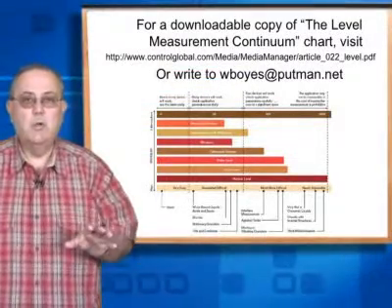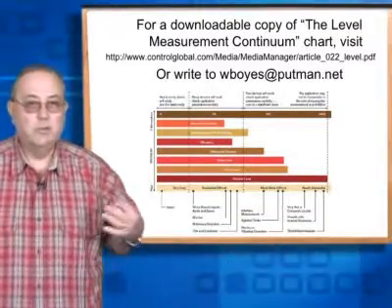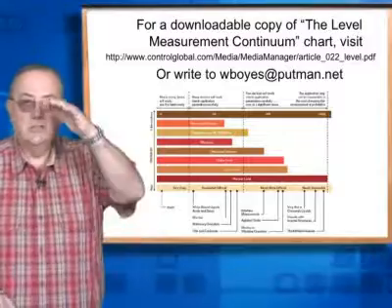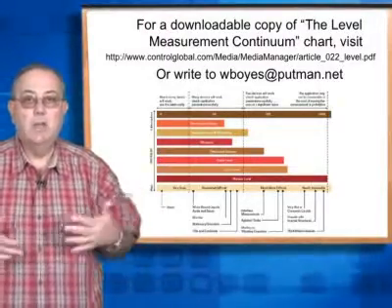You must always remember that you are not measuring level. You're measuring pressure, pressure differential, distance, capacitance, admittance change, or change in received radiation.